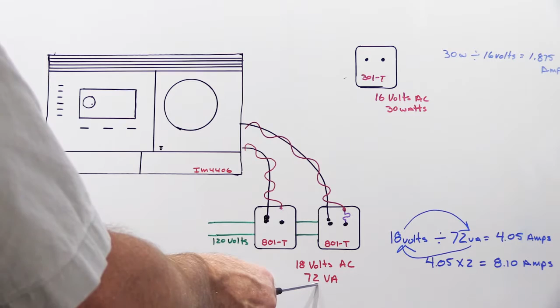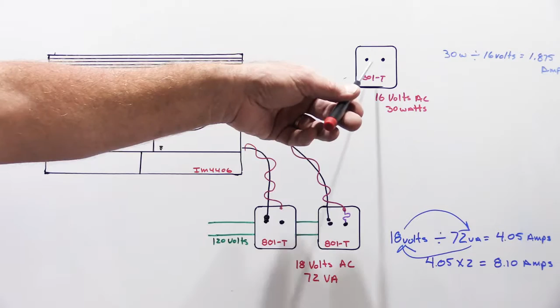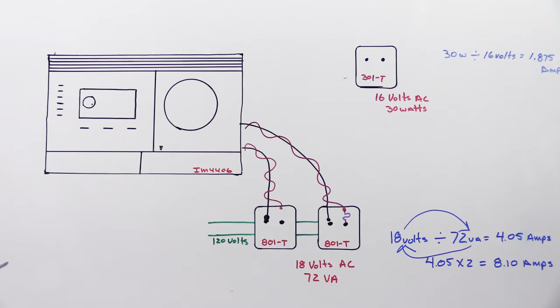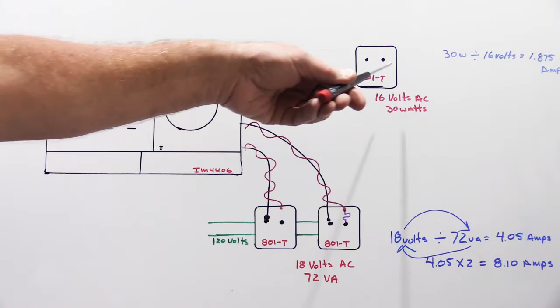So while a 301T is not a permanent solution or replacement for a blown up 801T, it is perfectly acceptable to use as a testing transformer. And if you do the calculation, oh wait, look, I got it written right this time. It's 30 watts divided by 16 volts, which gives us 1.875 amps, which you can see is less than half of the amps provided by a single 801T. So this is undersized and it cannot be used for permanent use. However, for short-term testing it works really well, and one of the reasons is that 301Ts don't have fuses built into them.